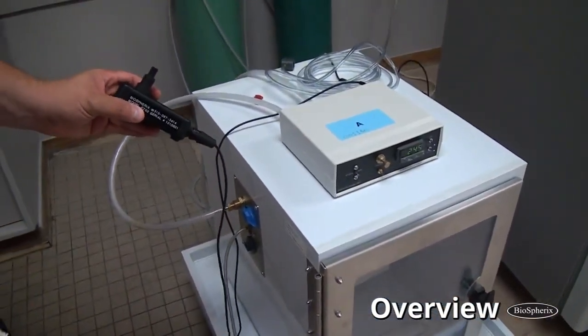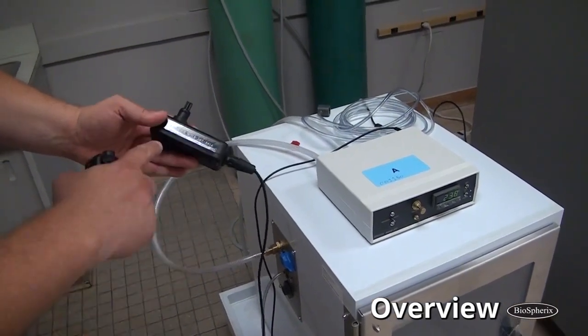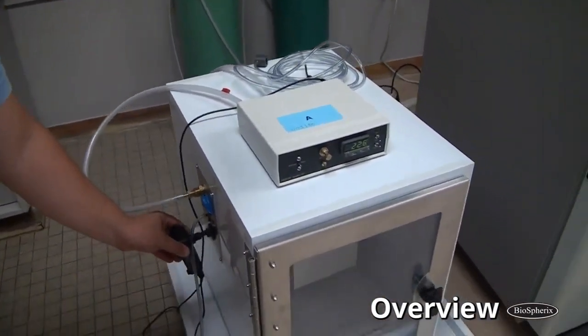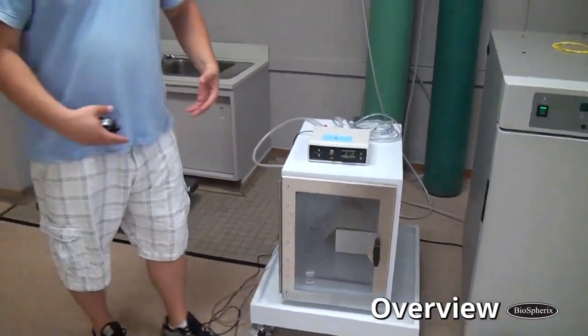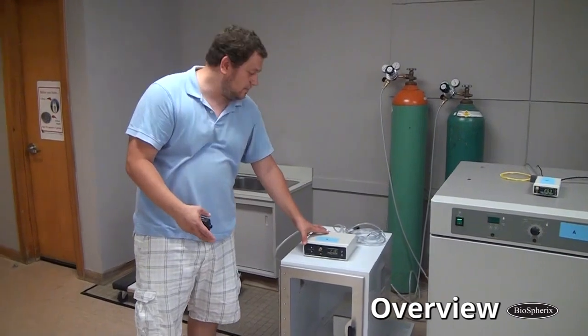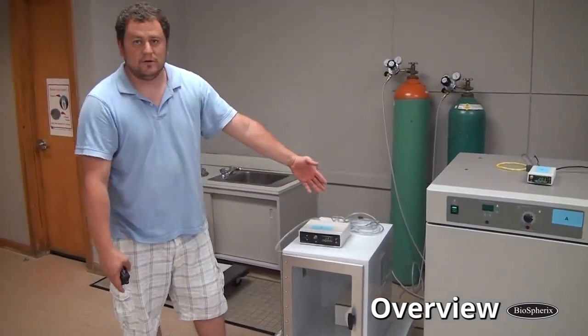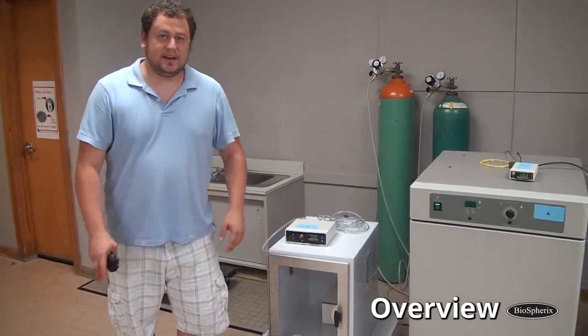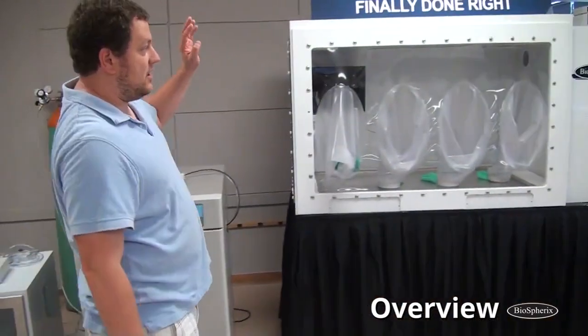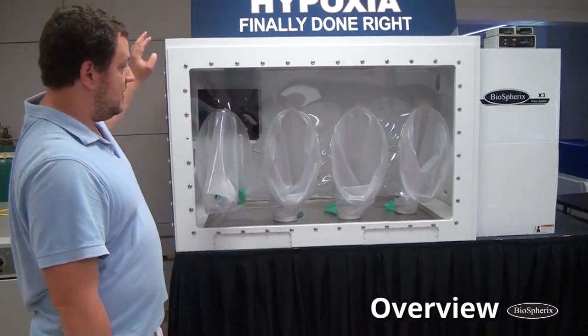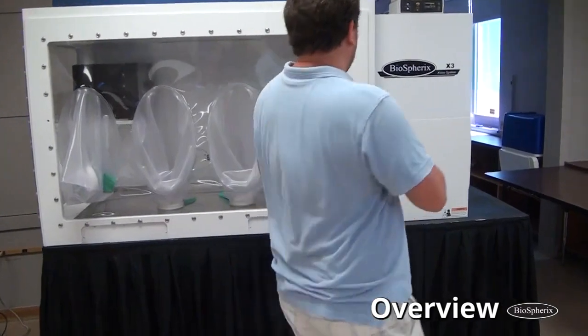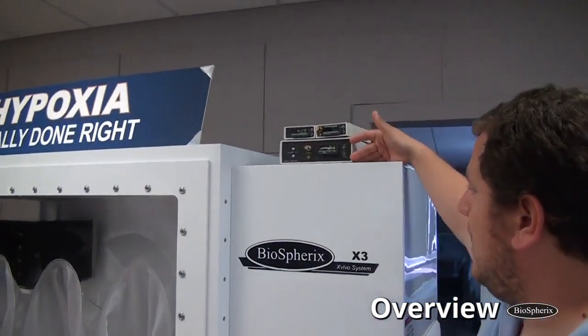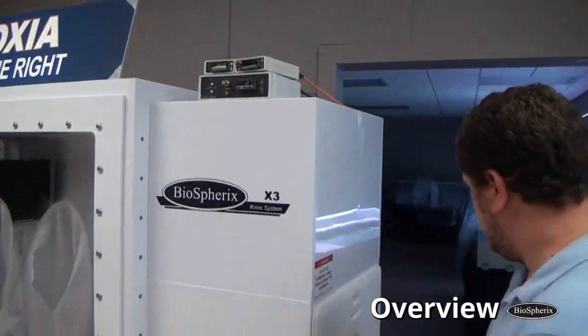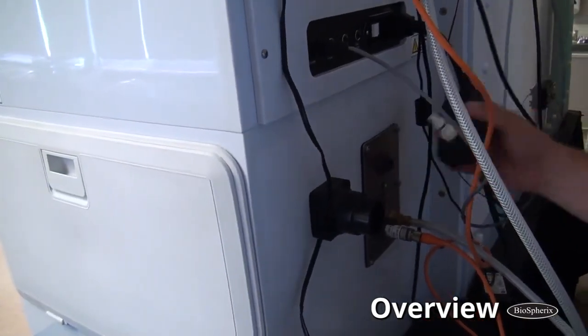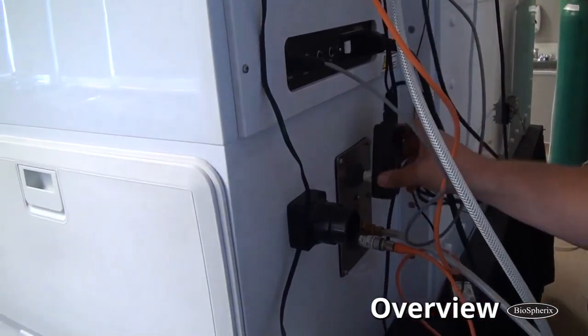As you can see, this one has a different color flow diverter, but it's the same sensor, model E702, found right there. Some animal setups have a dual redundant controller for the fail-safe setup. It would just be two of these next to each other, so you would have two sensors, but again, calibration is going to be exactly the same. Or finally, any of our X3 independent series, the glove boxes, they're all going to have a ProOx model 360 as well. Same sensor is used to control oxygen, and that's going to be found in back here on the buffer chamber, right on the adapter plate.